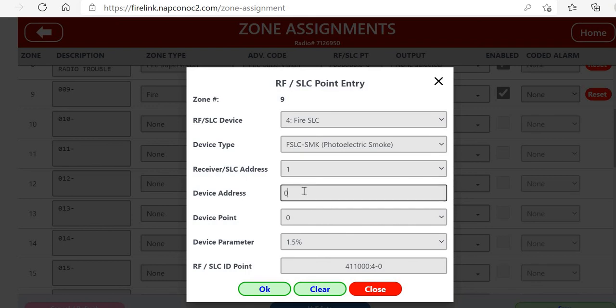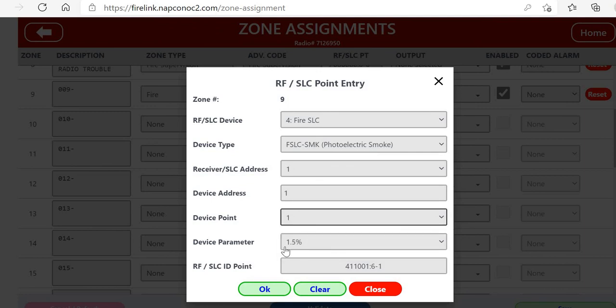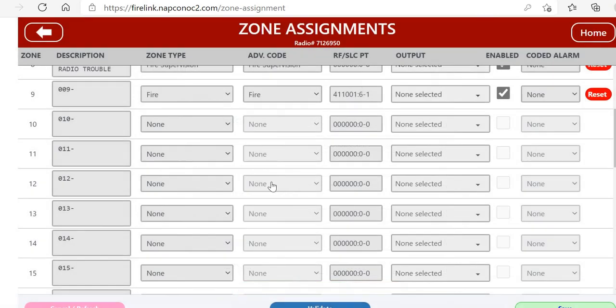The device address - this is going to be the actual physical address that was programmed into the detector or the module. You can have up to 126 addressable devices on an SLC card. The Firelink only takes 32 zones, and remember we can map any SLC address to any zone.